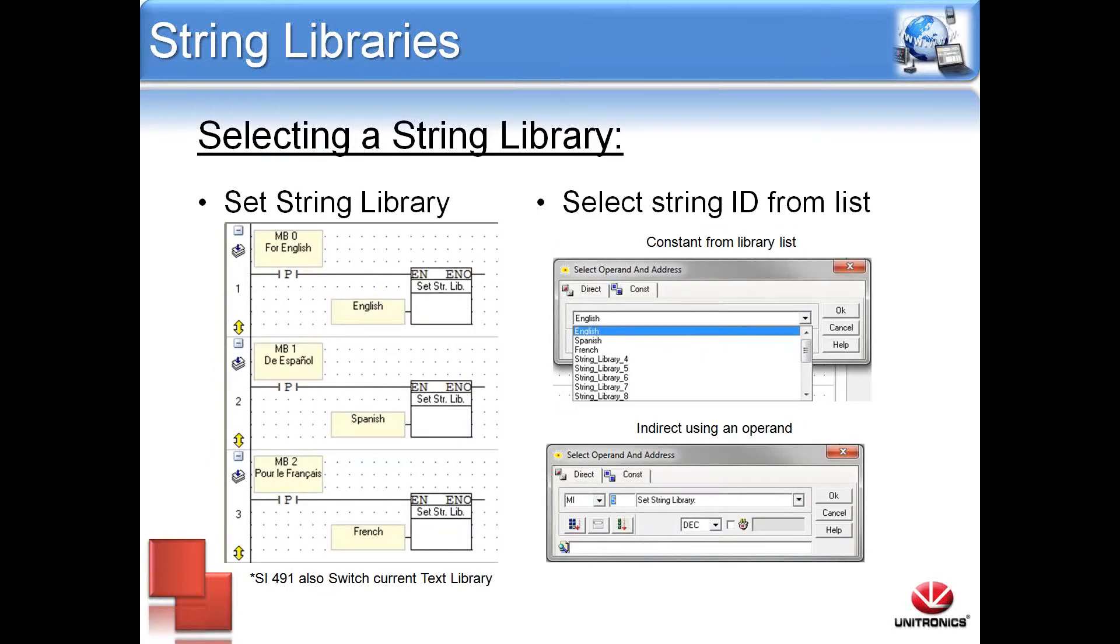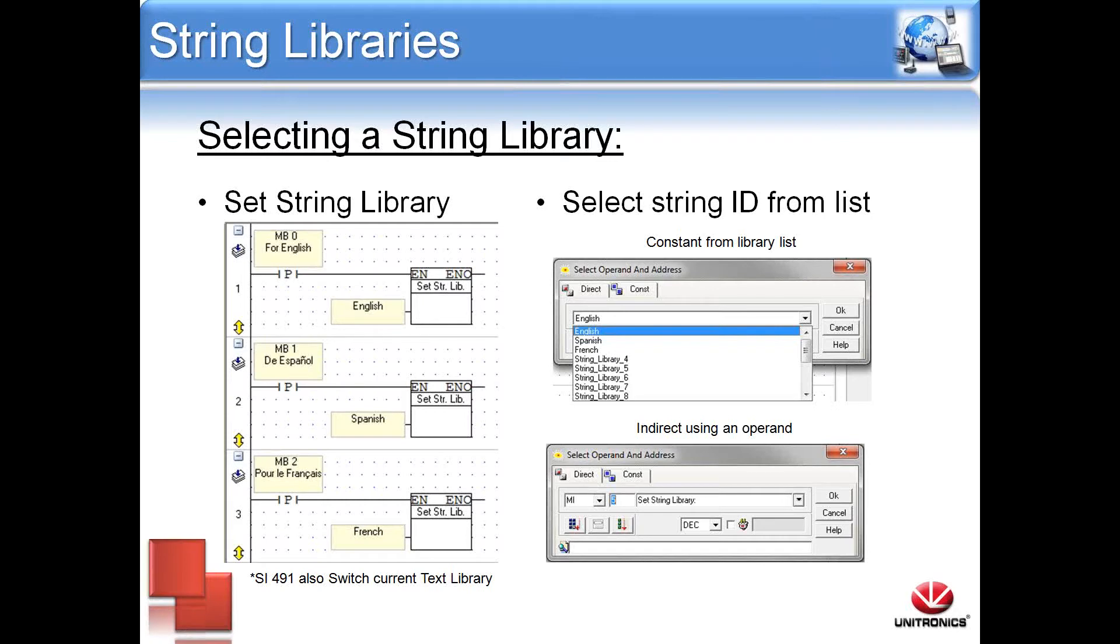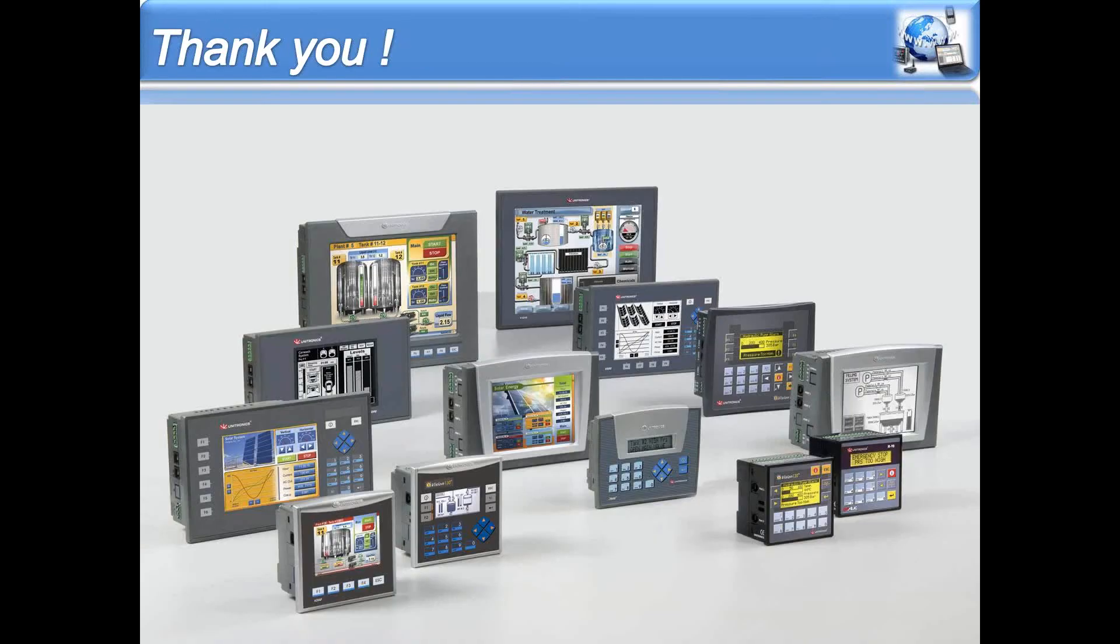It is also important to know how to select the specific string libraries. There is a function block within VisiLogic to set the specific string library. This can be chosen as a constant from the library list using a drop-down menu, or indirect using an operand as a pointer. Also, SI 491 is the switch current text library system integer.